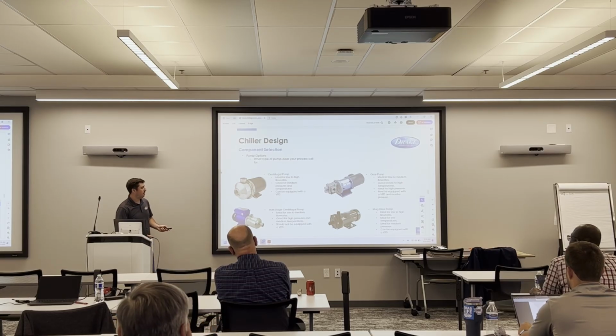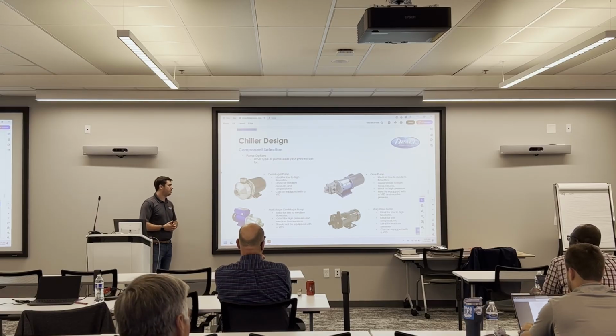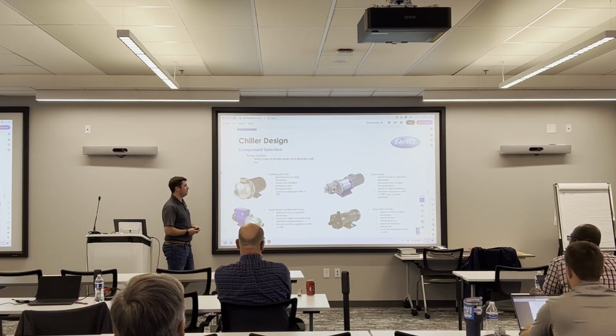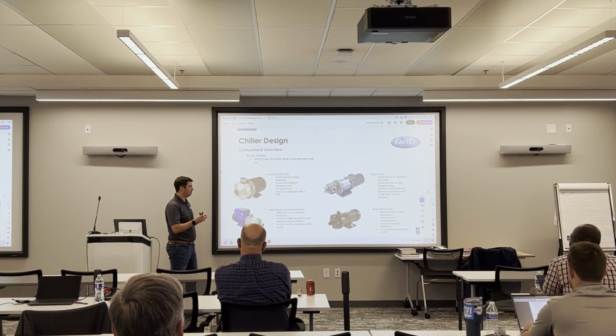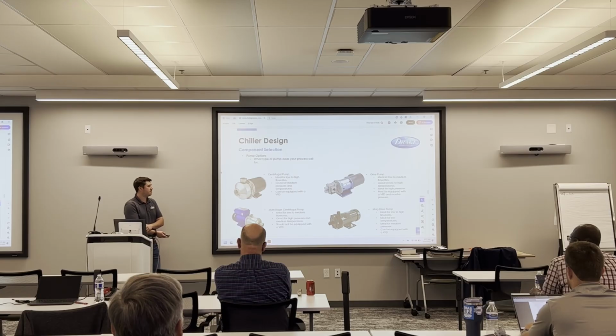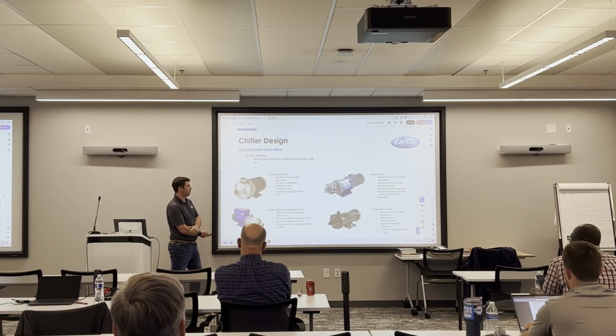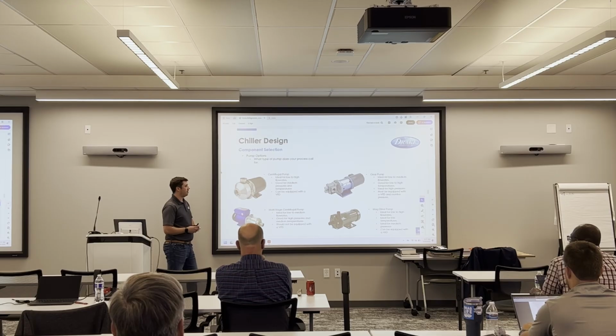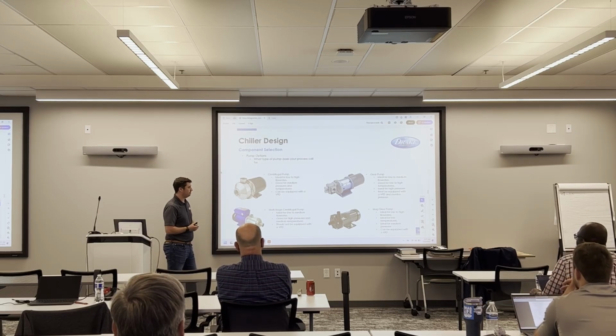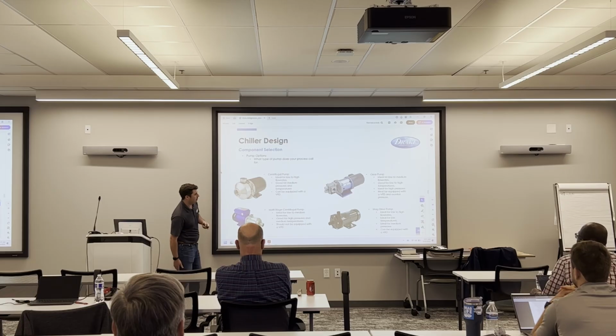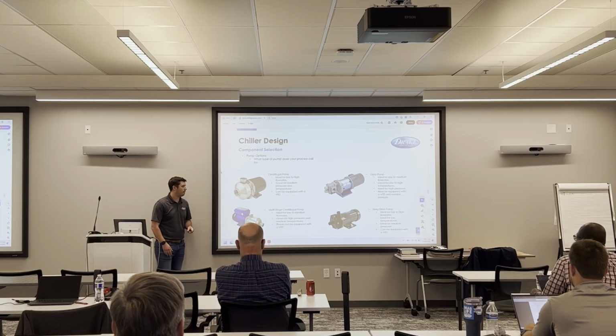And then down below is what I call a mag drive pump, magnetically driven. It has an impeller, but it's not physically attached to a motor shaft. Just like its name, it's a magnetically driven impeller. So it's great for low temp applications, especially when your fluid temperatures get to about negative 20 degrees and below. You're going to have significant heat transfer from the impeller to your motor. When that happens, you can end up seizing up your motor because it's going to get too cold. So what we do is we implement magnetically driven impellers, where the motor doesn't actually physically touch the fluid. Ideal for low temperatures, ideal for medium pressures. You can also equip this type of pump with a VFD.